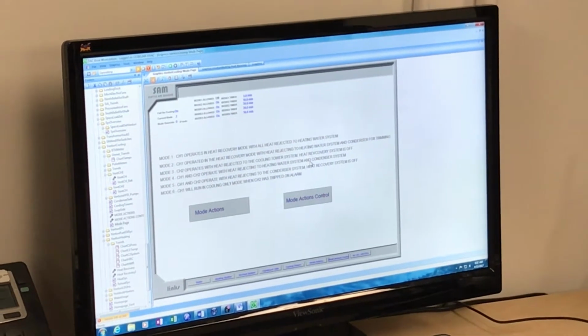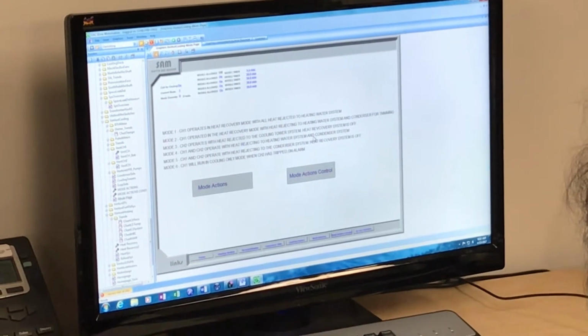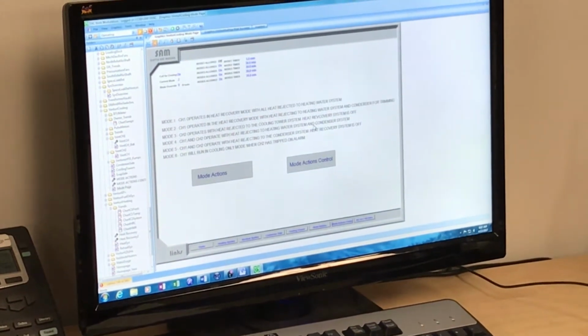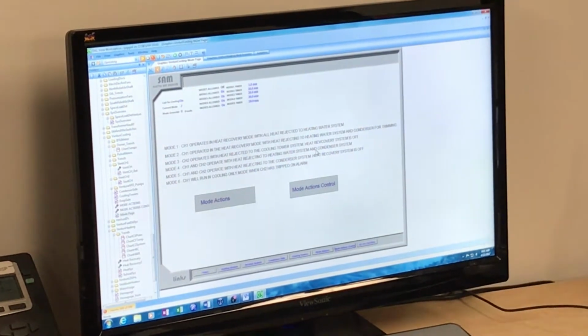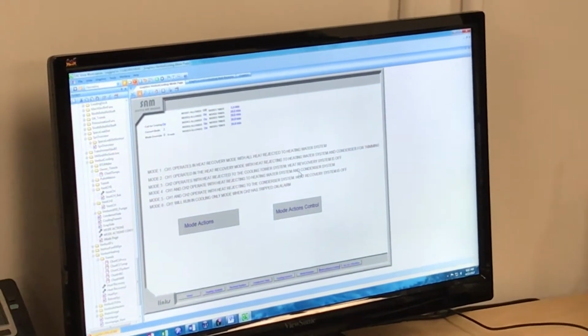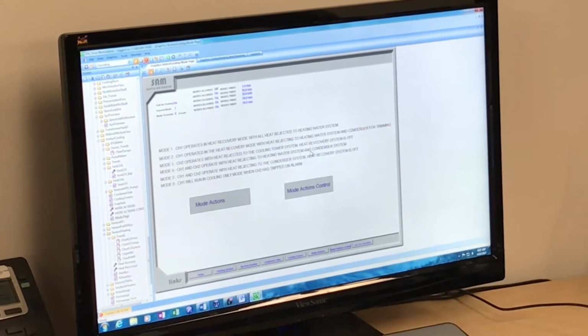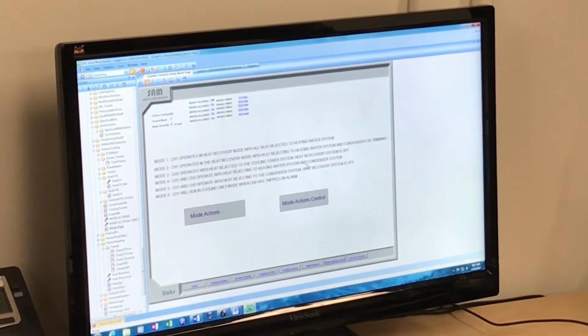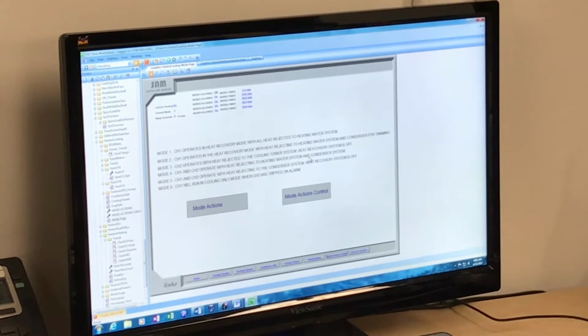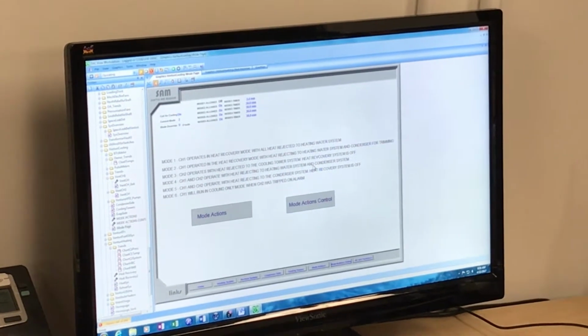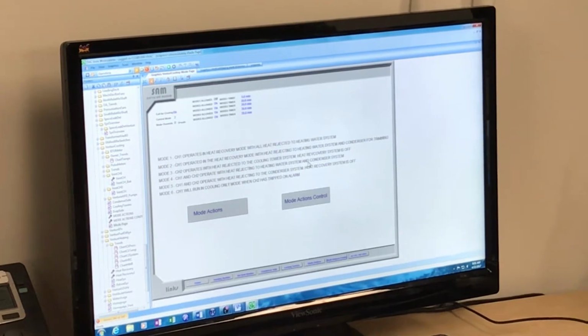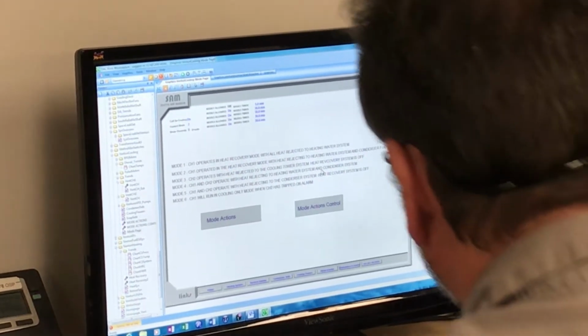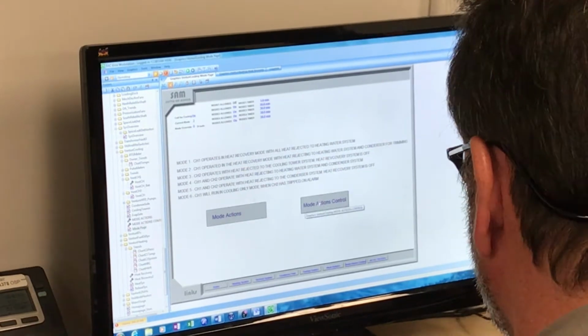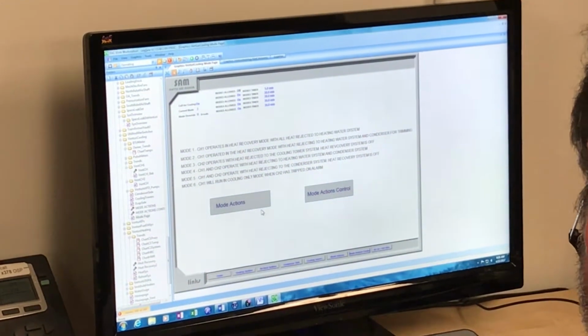So in mode 5, you still have both chillers operating, but all the heat is being rejected to the condenser system, and the heat recovery system is off. It's really more like an 85-degree day where it's very hot outside. You need cooling load, and there's a very low heating load requirement. Then you are going to run the 2 chillers in cooling mode with no heat recovery. And in case you have some heat demand, you probably will try to satisfy that with the steam heat, just a little bit.